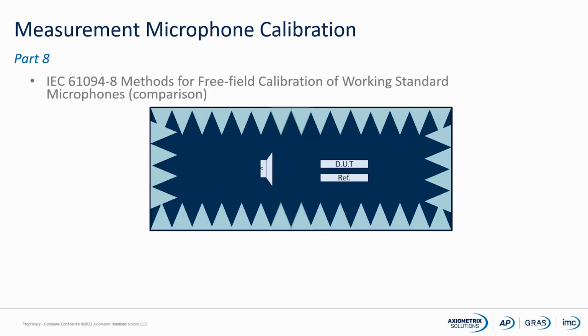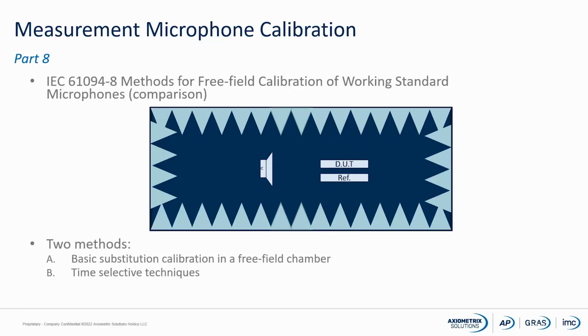If we look at the methods for free field calibration according to the working standard, it is a comparison method. So we have a setup like the one we have here, where we have a reference microphone and a microphone under test. We have a sound source, and we normally use an anechoic chamber. There are actually two methods. We can either use, as mentioned here, an anechoic chamber or a free field chamber, or we can use time selective techniques.